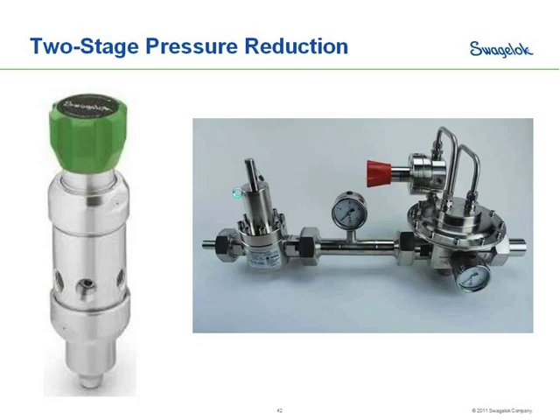Here's another question. Can you discuss the difference between liquids and gases in regulators? Okay, good. So the difference in liquid and gases in regulators really has to do with sizing. Liquids are a little bit more straightforward because they're non-compressible. So whatever your flow coming into your regulator is, it has to be the flow that's coming out. There's no way to compress it internally in the regulator. So it's a little bit more straightforward on sizing. Gases are a little bit different in sizing because you can have some compressibility going on. So there's different sizing methodologies when looking at gases versus liquids in the regulators.